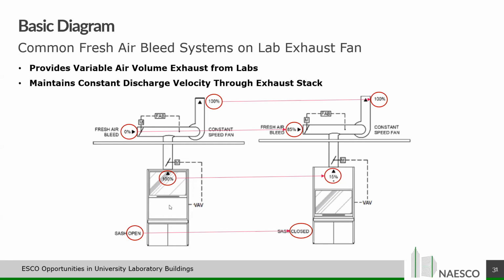Now, in this scenario, when the hood is open, the sash is open, 100% of the air is coming up through the fume hood, past the damper, 100% is going out through the stack, and you're discharged at 3,000 feet per minute. So we've got a closed fresh air bleed damper right here, and we've got our discharge velocity up here. So when you close the sash on a VAV fume hood, now you reduce your exhaust by 85%. This damper in the exhaust duct chokes down. This fresh air bleed damper on the roof opens up and allows 85% of unconditioned outdoor air to join your lab exhaust, and you discharge still 100% of the volume. So your fan is at constant volume, constant speed. Your discharge velocity does not change, but you're taking unconditioned outdoor air in place of the lab exhaust.